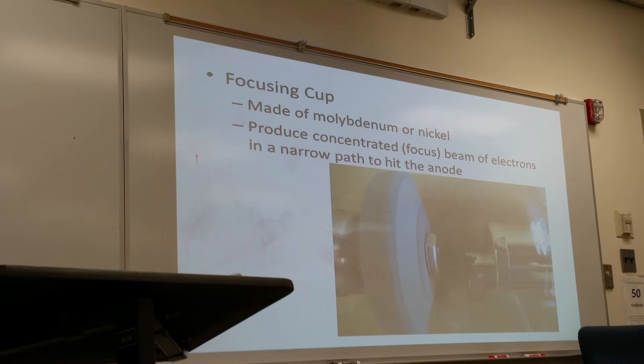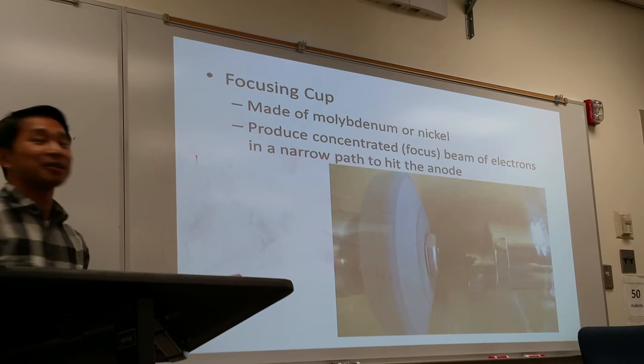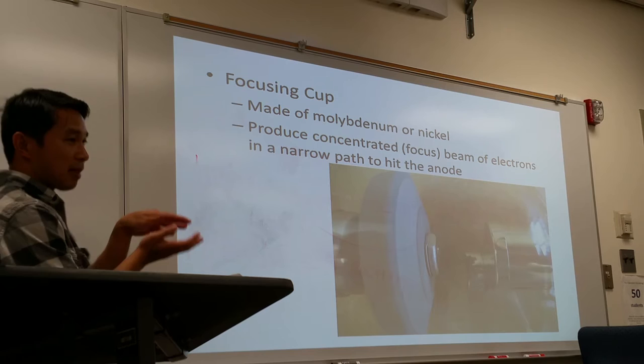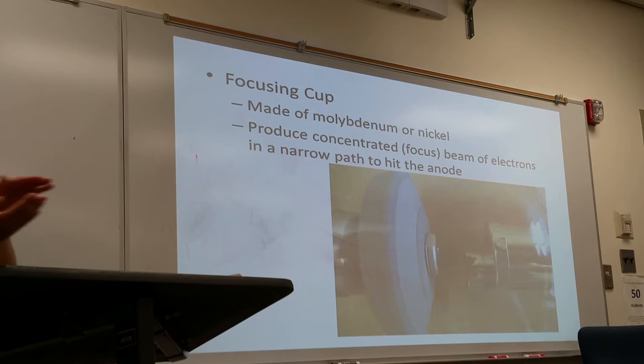The other part of the cathode side is the focusing cup, generally made of molybdenum or nickel. The purpose of the focusing cup is to concentrate the electrons that are about to escape, directing them toward the anode side through a very narrow path.